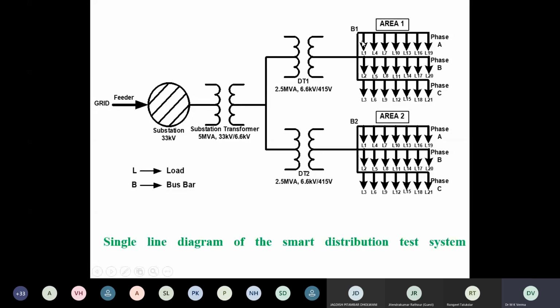Once illegal loads are connected, what happens? The phasor sum of currents measured by all smart meters will differ from the current at the substation, because the DT secondary current is the phasor sum of all legal currents as well as illegal currents in different phases. If there is no theft, the DT secondary current in all the phases will be almost equal to the magnitude of the phasor sum of current of all smart meter readings. But in case there is some theft, the phasor sum of smart meter currents measured by smart meters will differ from the DT secondary current magnitude.